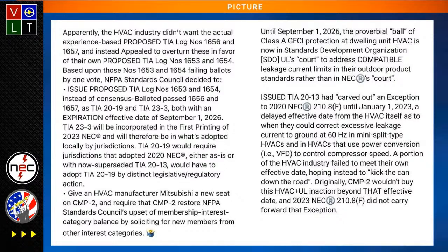Now, if you look at that last sentence, what do they say? Originally, code making panel 2 wouldn't buy it. Now watch this: HVAC plus UL inaction beyond that effective date, 2023 NEC 210.8F did not carry forward the exception. So now you're telling me that because you required something, the HVAC manufacturers and UL should have jumped on that right away and just done exactly whatever it is you told them needed to be done? I've heard someone on the panel say, I'm not going to say his name, 'we dictate that you got to have that GFCI protection.' I got news for you, you don't dictate nothing. They just write the code and then they interpret it however.